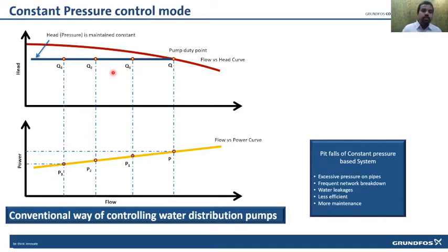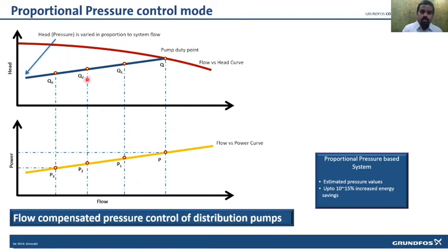So we are moving from a constant pressure approach to a proportional pressure approach, which means, very simply, that we are taking friction loss compensation as an additional benefit, and our set point will be dynamic. When there is a reduction in the flow consumption, the set point reduces automatically, and hence the power consumption will reduce. So this is the concept we are trying to bring with the help of proportional pressure. It not only saves energy, close to 10 to 15%, it also saves water consumption.